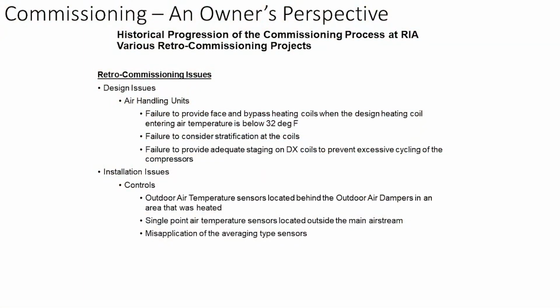We also did some retro commissioning. There's a class that the Corps of Engineers teaches that I took. It was online during the pandemic that dealt with retro commissioning. So we actually did retro commissioning, or looking at a couple of the buildings. And we found some really strange problems. One was some of the designers didn't put face and bypass on the heating coils that were subject to temperatures 32 degrees and below. I guess they assume that it's going to operate 100% of the time.